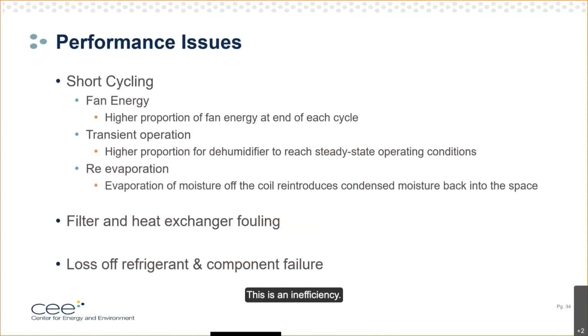This is an inefficiency. Secondly, as the dehumidifier warms up to get to steady state, it goes through the warm-up process, and it has to reach its operating points. This is another inefficiency that scales with the inverse of cycle length. However, the most pernicious inefficiency for short cycles in dehumidifiers is, again, tied to this fan energy at the end of the cycle. This fan is blowing moisture off the evaporator, and it's blowing it right back into the space. Energy was already used to condense that moisture, so all that energy is wasted. In the shortest cycle, we measured that this can reduce efficiency by a staggering 35%.